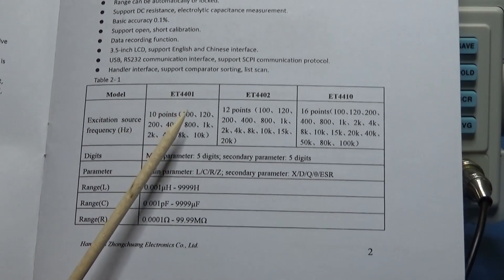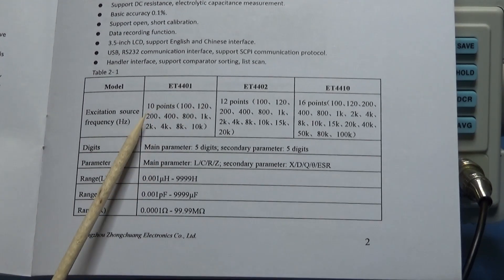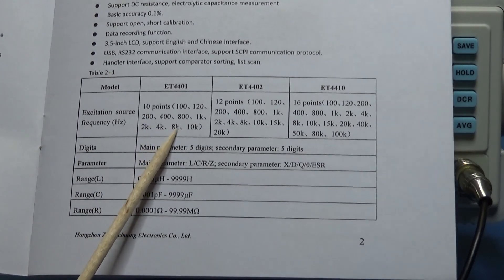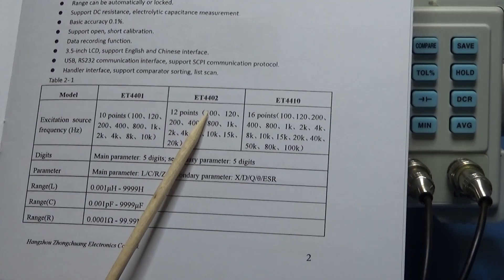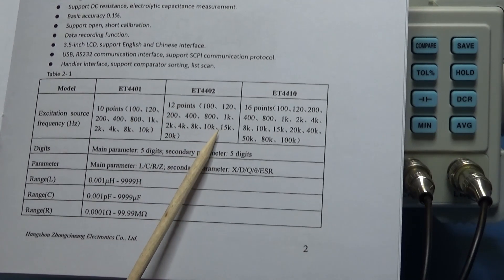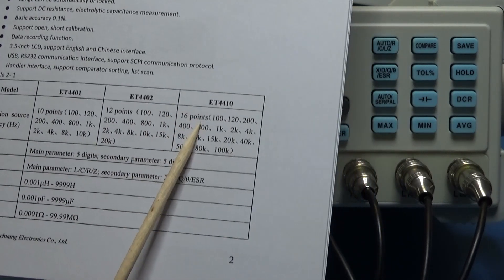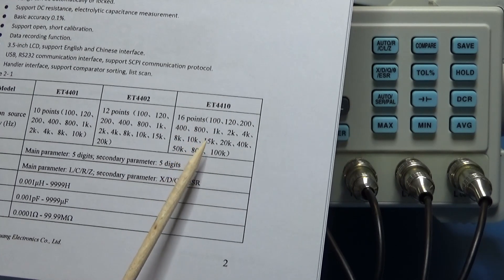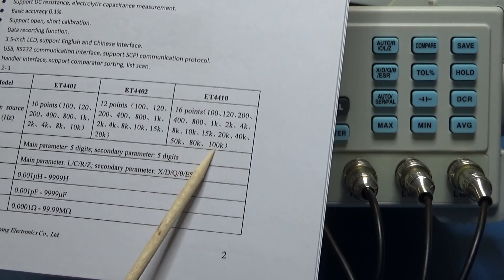In the specifications it sets points but points is the steps. So for 10 kilohertz it will go for 10 points: 100 hertz, 200, 400, 800, 1 kilohertz, 2 kilohertz, 4 kilohertz, 8 kilohertz, and 10 kilohertz. For the 20 kilohertz it says 12 points. So after 10 kilohertz we go to 15, 20. And 16 points for the 100 kilohertz. That means after 15 we go to 20 kilohertz, 40, 50, 80 and 100.